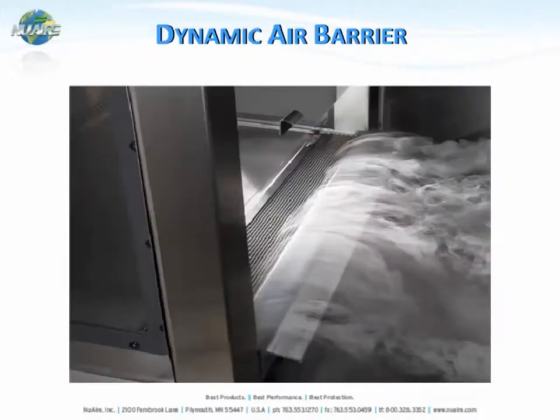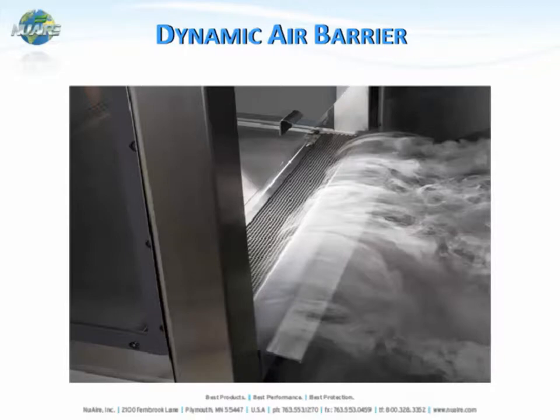Personnel protection of the biological safety cabinet is provided through a dynamic air barrier through the front access opening. An airflow velocity of 100 feet per minute minimum velocity is used to provide protection from any contaminants leaking out of the cabinet and affecting the laboratory space or the technicians working within the cabinet.